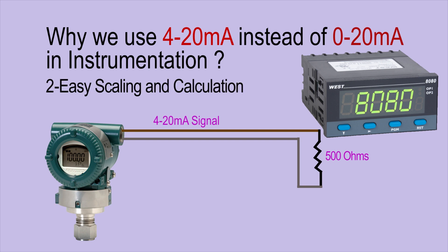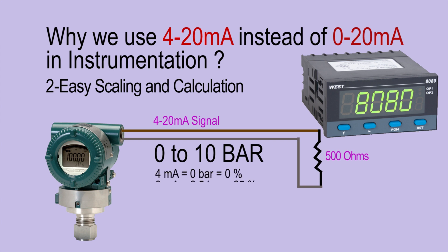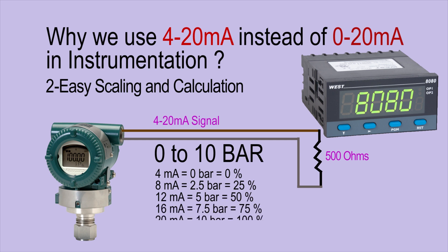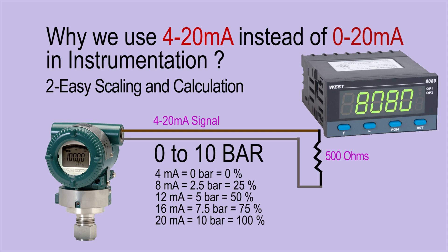Reason number two is easy scaling and calculation. For example, using a 0 to 10 bar pressure transmitter, it is very easy to scale 0 to 10 bar across the 4 to 20 milliamp signal. At 4 milliamps the pressure is 0 bar, which is 0% of the output. At 8 milliamps the pressure is 2.5 bar, about 25% of the transducer signal. At 20 milliamps the pressure is 10 bar, which is 100% of the transmitter output signal.